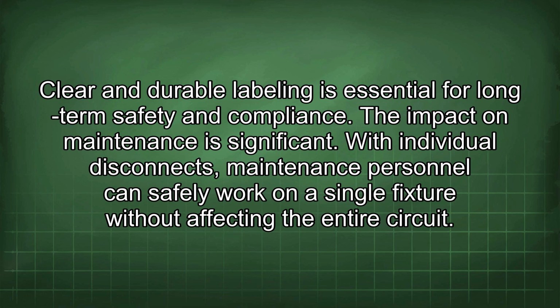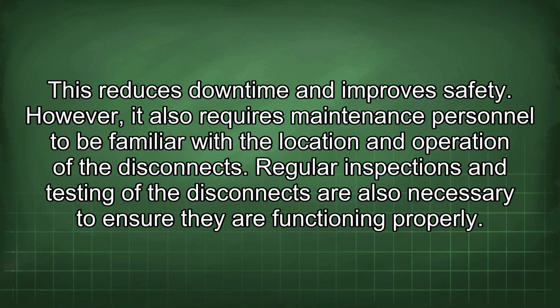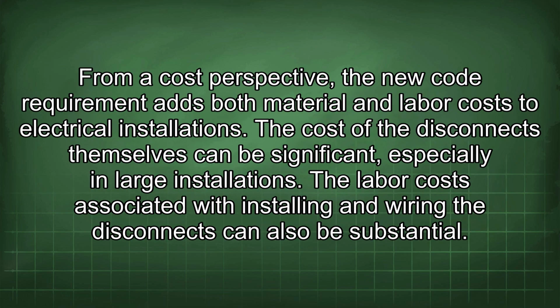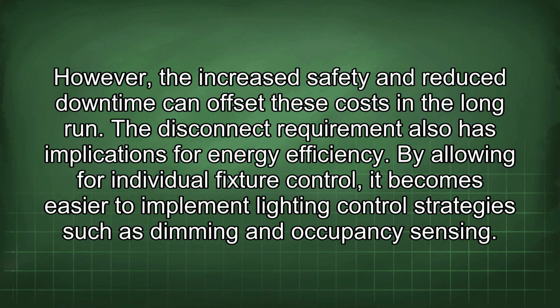The impact on maintenance is significant. With individual disconnects, maintenance personnel can safely work on a single fixture without affecting the entire circuit. This reduces downtime and improves safety. However, it also requires maintenance personnel to be familiar with the location and operation of the disconnects. Regular inspections and testing of the disconnects are also necessary to ensure they are functioning properly. From a cost perspective, the new code requirement adds both material and labor costs to electrical installations. The cost of the disconnects themselves can be significant, especially in large installations. The labor costs associated with installing and wiring the disconnects can also be substantial. However, the increased safety and reduced downtime can offset these costs in the long run.